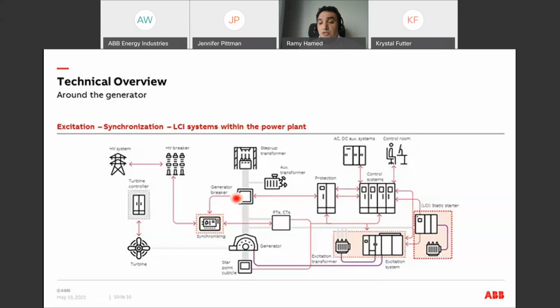The synchronizer will adjust the voltage, the frequency, and wait for the phase angle of the generator. Then it will issue the command to close the generator breaker. The synchronizing relay is such a critical component that it can cause so much damage to the system.